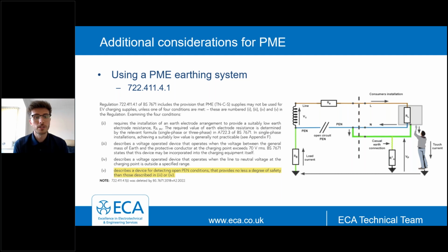So a PME earthing facility, where the charge point could be located outdoors or is expected to be used outdoors, cannot be used to supply EV charging equipment unless one of the following 4 conditions is met. These are indent 2 to indent 5. You'll see I've got indent 5 highlighted. My main area of focus will be on that, because it's probably the most common measure applied when looking at our mode 3 charging. So we'll summarize the first few to start with.